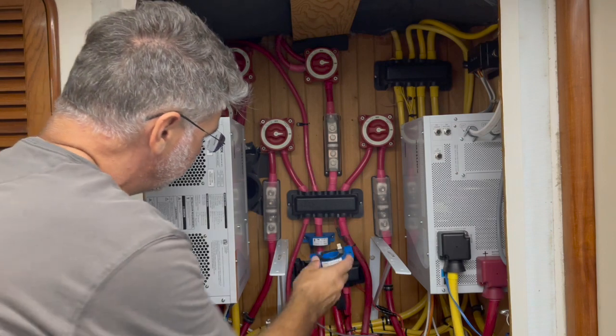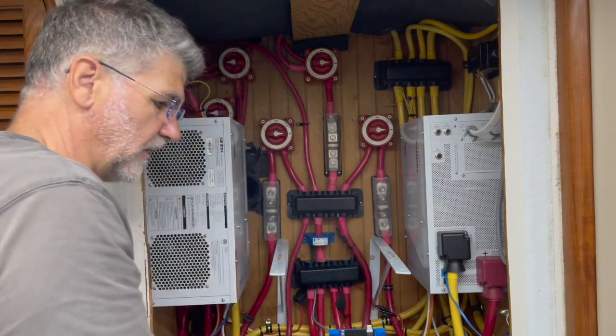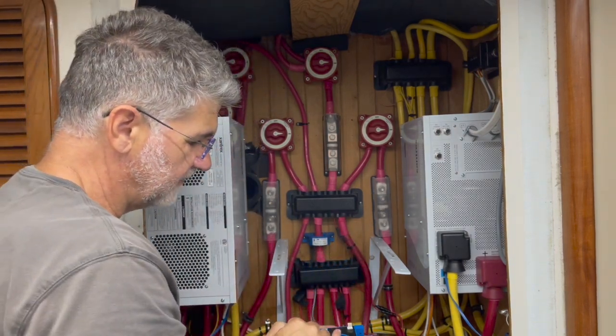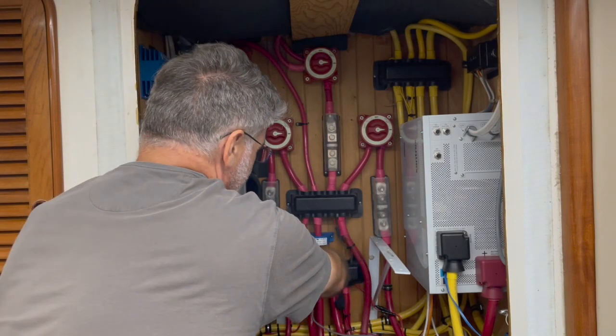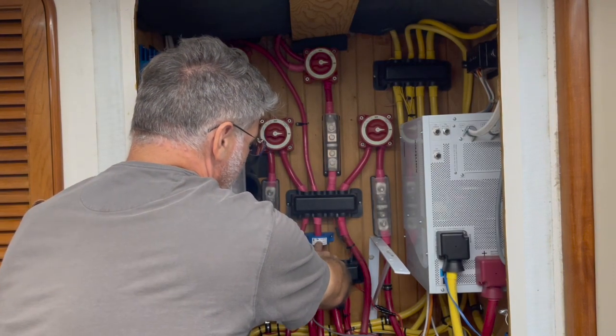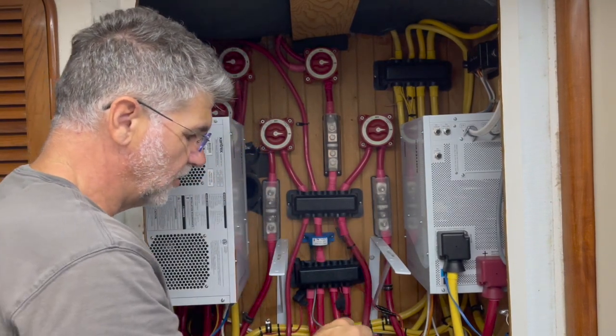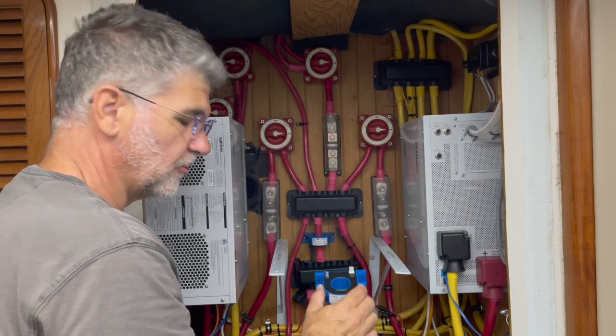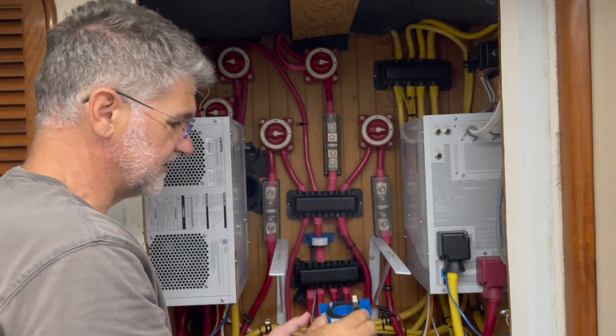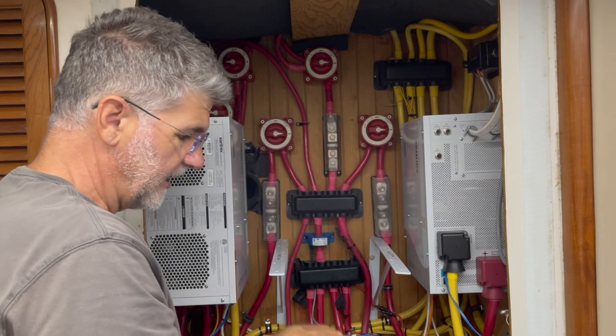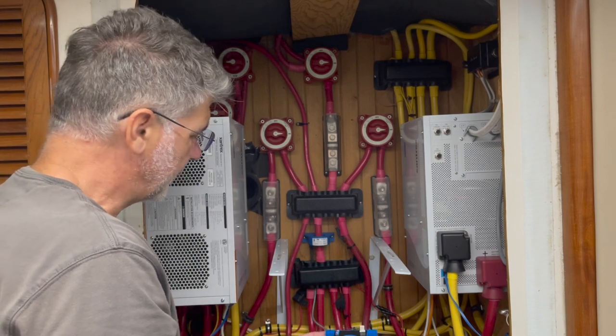So I'm going to replace this right now and put it in place. One thing I need to do, just to make sure everything's good, is disconnect the lead wires from this Hall effect sensor, hook it up, and zero it out with the Maretron system, so it knows there's no amperage flowing through. It's basically just a calibration.